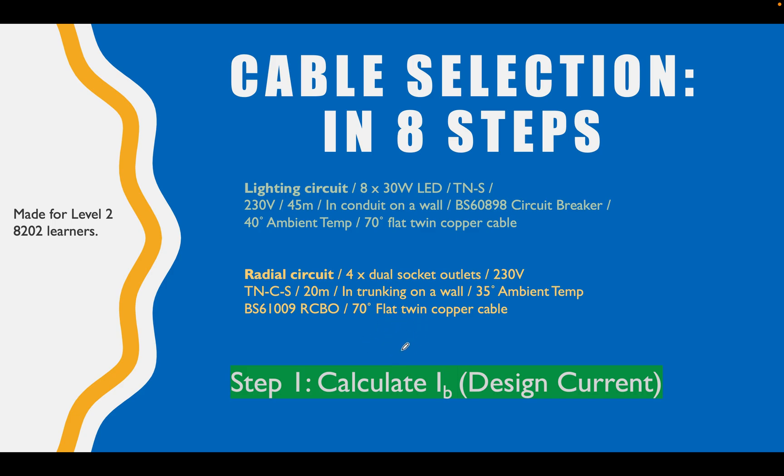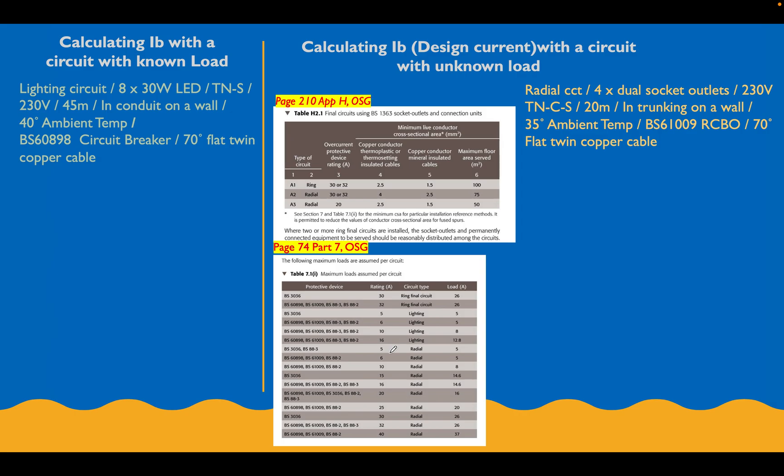Let's calculate the design current for both these circuits. Starting with our lighting circuit - we've got 8x30 watt LEDs, that's really the only bit we're interested in at the moment along with the 230 volts. We're calculating our design current which is our Ib. The Ib is our design current and that's going to be equal to the power rating of our circuit divided by the voltage. We're looking for the current, we need the power and the voltage - you'll recognize this triangle we've done many times. We're looking for this value, so we just divide power by voltage.